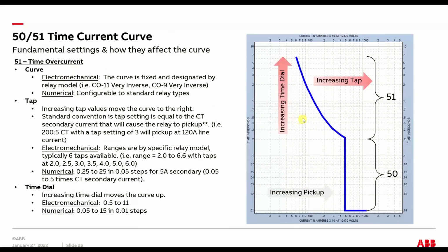Here's some explanations on the settings of the relay. It's back to what I was talking about: tap, time dial, and then curve. So this is for time overcurrent. For your time overcurrent, you have your time dial, which essentially moves the curve up and down in time on the time axis, and then your tap, which essentially moves the pickup left and right on your ampere axis.